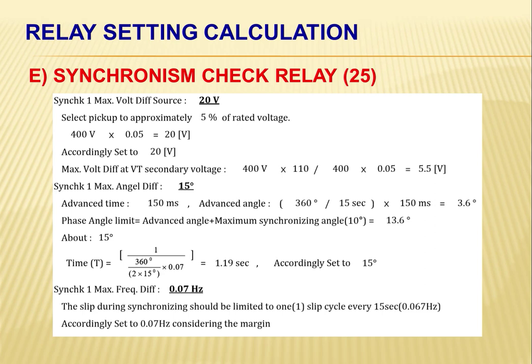It is preferred that the voltage of 2 sources be as close to nominal as possible to avoid reactive power, or VAR flow. So here we use the maximum allowable value, which is 5%. So 5% of 400 volts, that's why we have here the 20 volt setting for the maximum voltage difference.